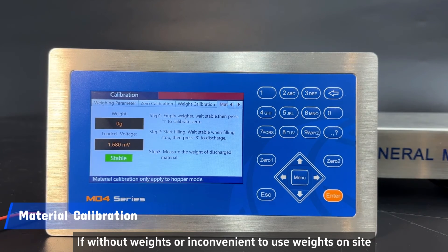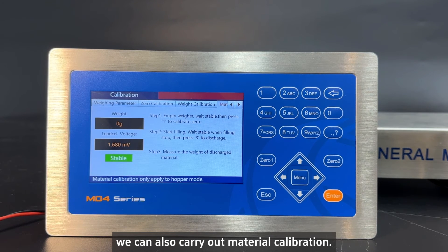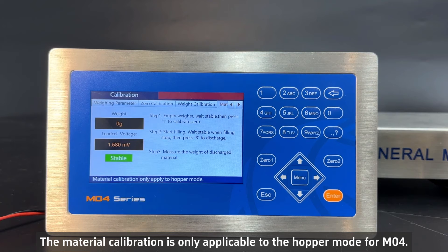If without weights or inconvenient to use weights on site, we can also carry out material calibration. The material calibration is only applicable to the hopper mode for M04.